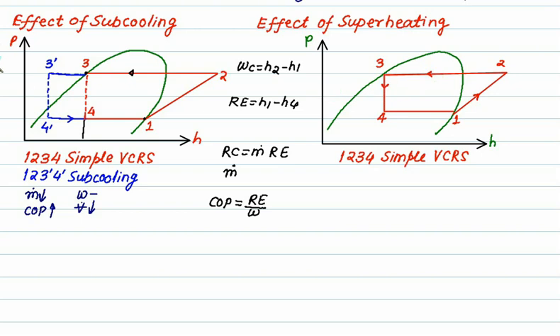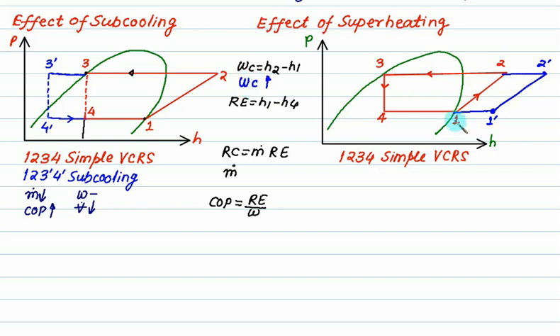Now we will discuss the effect of super-heating. The simple VCRS cycle is 1-2-3-4. Because of super-heating, point 1 will shift to the right side, and the graph moves right. With super-heating, h2-dash minus h1-dash is greater than h2 minus h1, so the work required by the compressor will increase. The refrigerating effect is h1 minus h4 for the simple cycle.